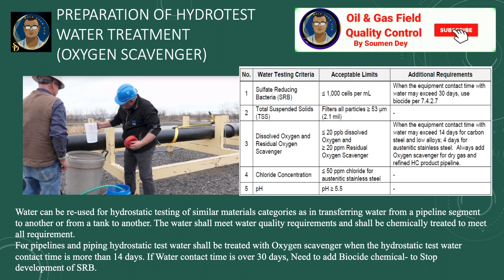Multi-component products as provided by chemical vendors are exempt from the pre-mixing requirement. Now let us discuss again the limits of the components present in the water. Sulfate reducing bacteria (SRB) count should be less than 1000 cells per milliliter; when equipment contact time with water may exceed 30 days, use biocides as required. Total suspended solids (TSS) — filters all particles greater than 53 micrometers or 2.1 mil. Dissolved oxygen should be less than 20 ppb, and residual oxygen scavenger greater than 20 ppm when equipment contact time exceeds 14 days for carbon steel and low alloys, and 4 days for austenitic stainless steel. Always add oxygen scavenger for dry gas and refined hydrocarbon product pipelines.